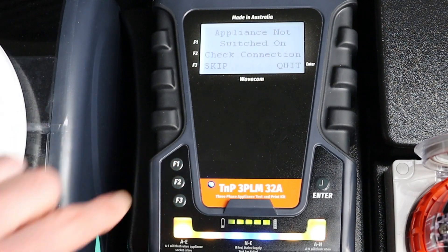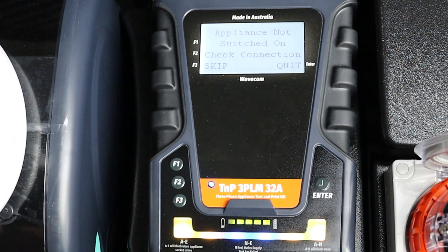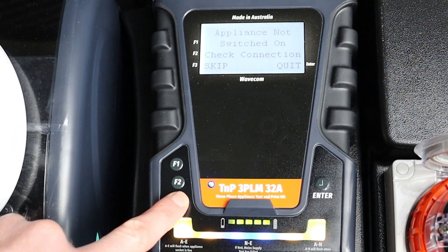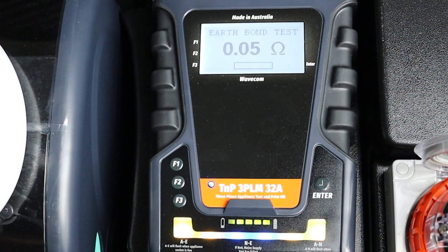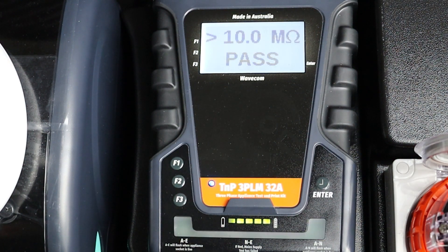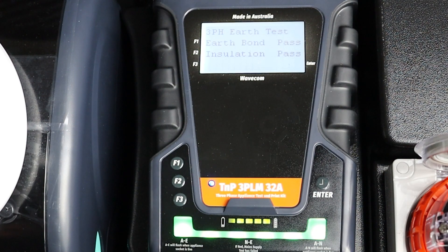To conduct a manual three-phase earth test, first navigate to Main Menu B using the Enter button. Then press F1 to begin the test. If your appliance does not have a power button or switch, you may need to override the connection check. The 3PL will begin testing the appliance, conducting each test in sequence. When the test is complete, the results will be displayed on screen.